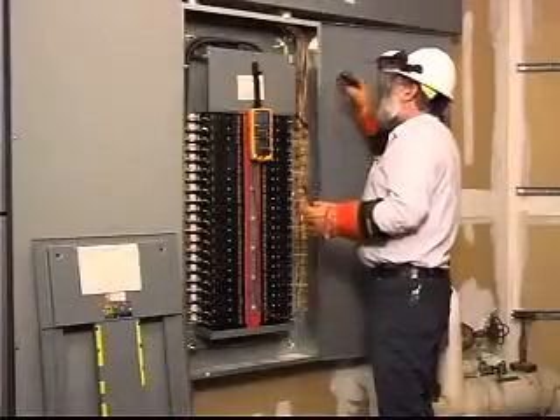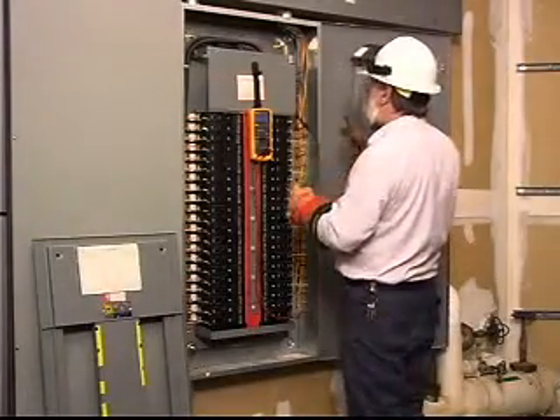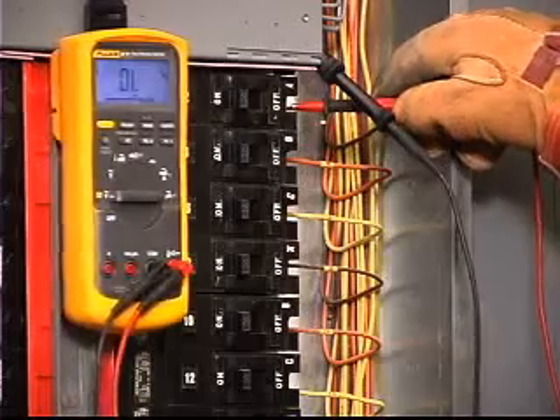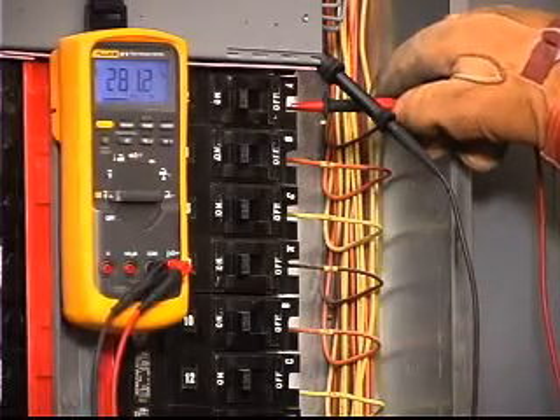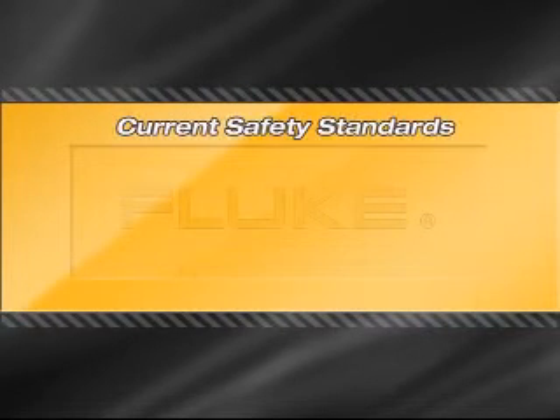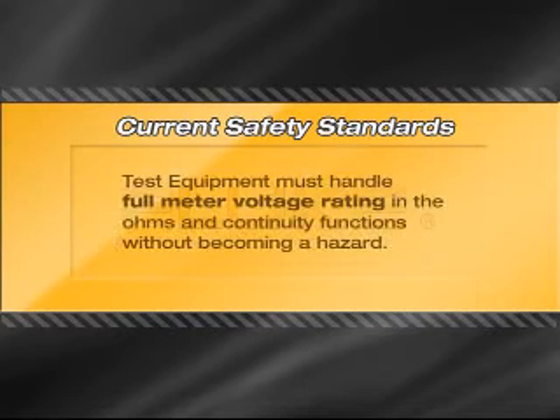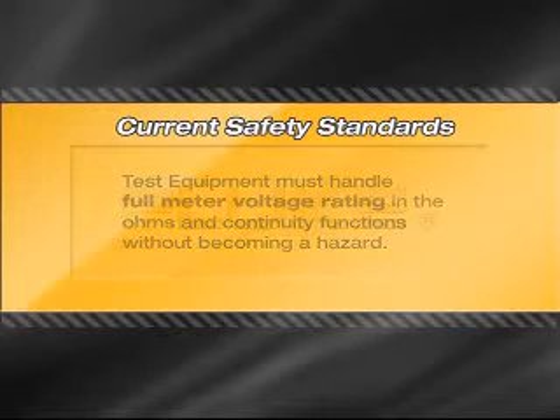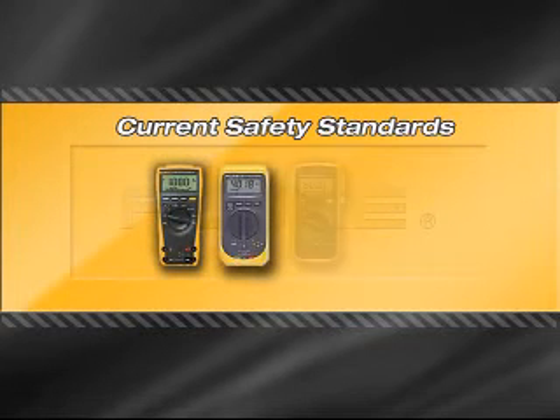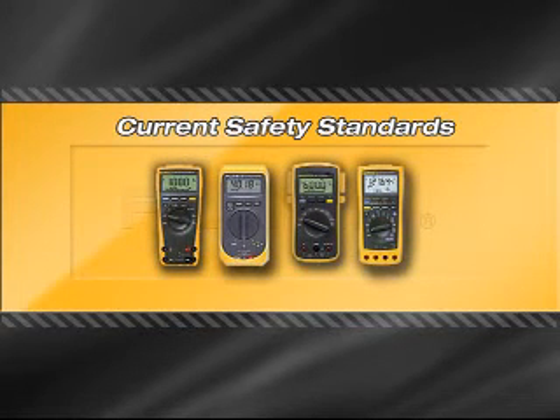Even the most careful of us will make mistakes. That's why, if an inappropriate voltage is applied, your meter should offer a margin of protection. This principle is so important that it has been written into current safety standards. The standards require that test equipment must handle the full meter voltage rating in the ohms and continuity functions without becoming a hazard. To meet the demands of today's high-energy, high-hazard workplace, quality manufacturers have re-engineered their test instruments to make them more reliable and far safer.